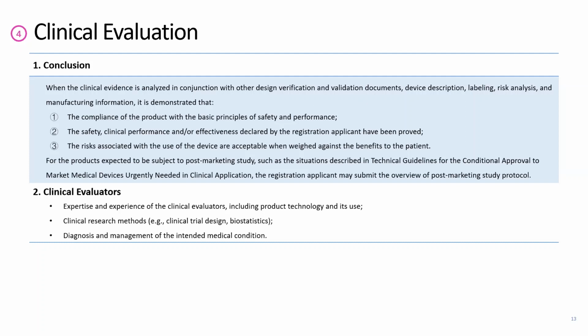The guidance also mentions that if the company wants to conduct a post-marketing study, we need to mention it, but this is not a must. But I know in EU MDR, it is a must. The company needs to emphasize it in the report. And the last is about the clinical evaluator. Previously, we didn't have this part, and here we need to mention whether the writer and the reviewer have the expertise to draft or review this clinical evaluation report. That's for the whole clinical evaluation report.